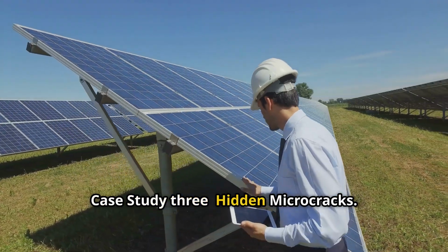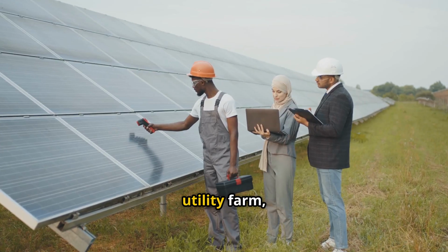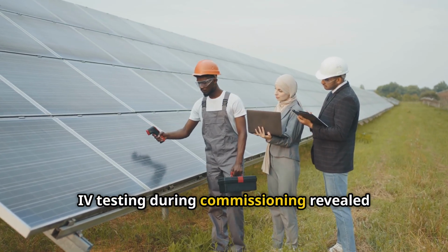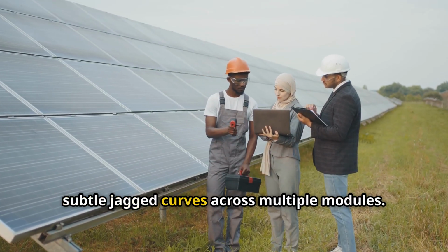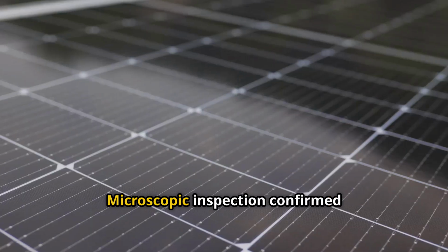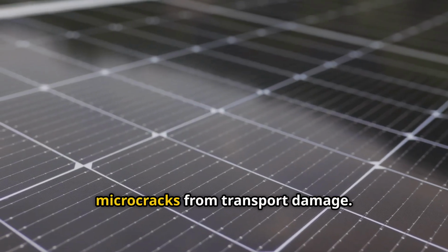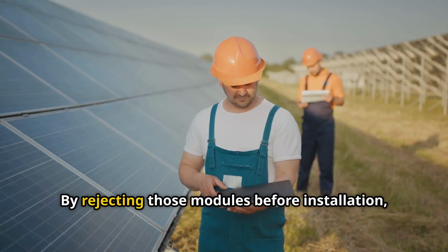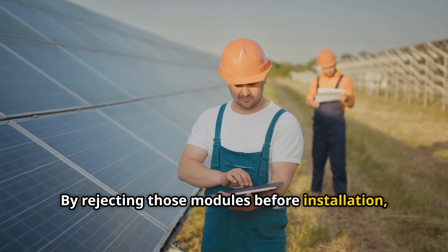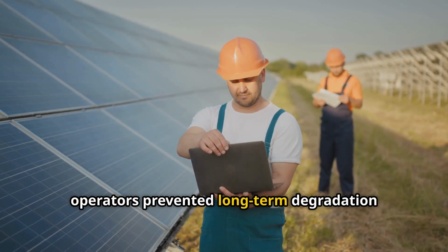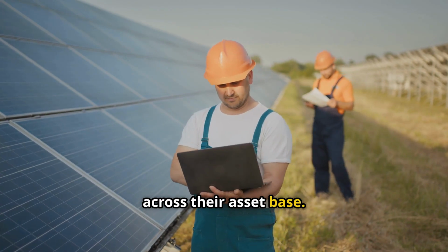Case study 3, hidden microcracks. In a US utility farm, IV testing during commissioning revealed subtle, jagged curves across multiple modules. Microscopic inspection confirmed microcracks from transport damage. By rejecting those modules before installation, operators prevented long-term degradation across their asset base.